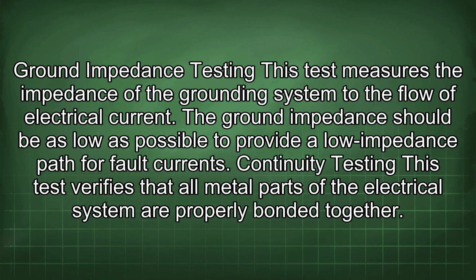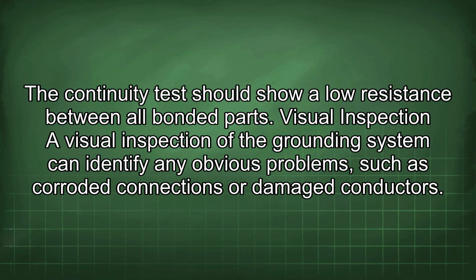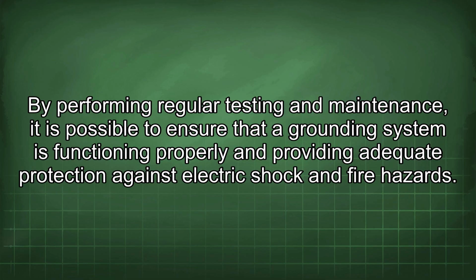Ground impedance testing. This test measures the impedance of the grounding system to the flow of electrical current. The ground impedance should be as low as possible to provide a lower impedance path for fault currents. Continuity testing. This test verifies that all metal parts of the electrical system are properly bonded together. The continuity test should show a low resistance between all bonded parts. Visual inspection. A visual inspection of the grounding system can identify any obvious problems, such as corroded connections or damaged conductors. By performing regular testing and maintenance, it is possible to ensure that a grounding system is functioning properly and providing adequate protection against electric shock and fire hazards.